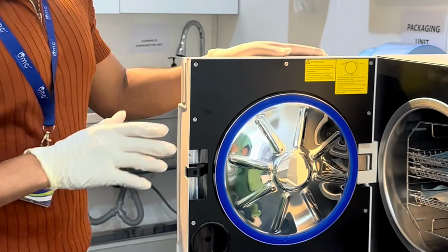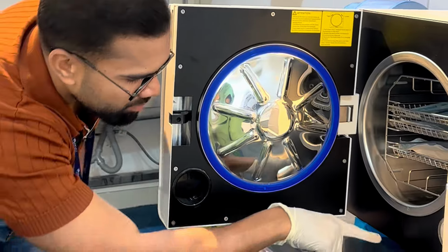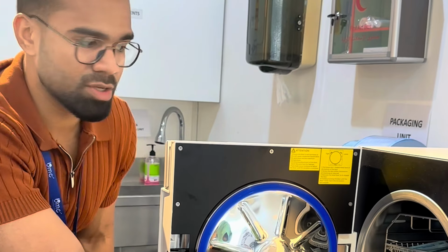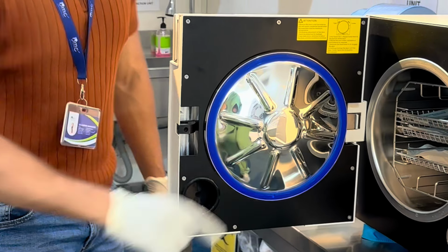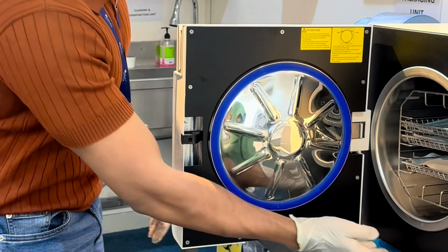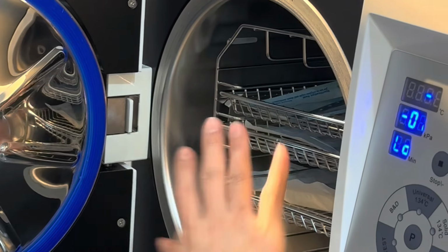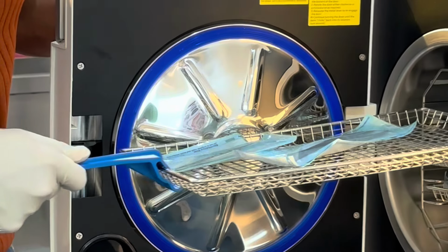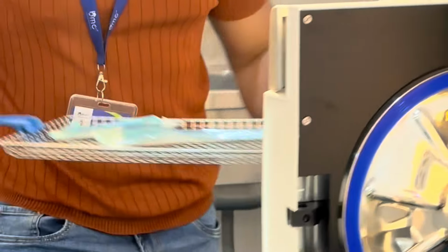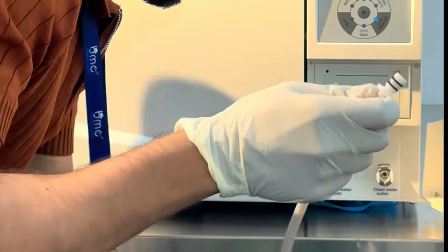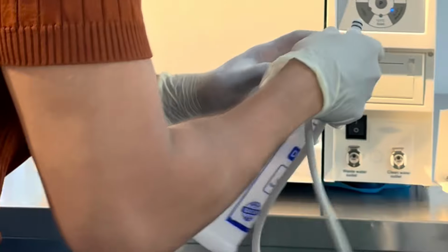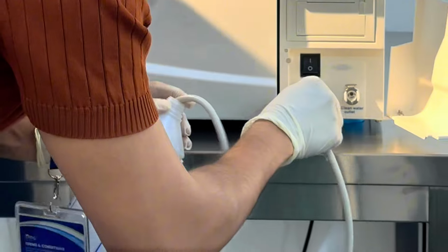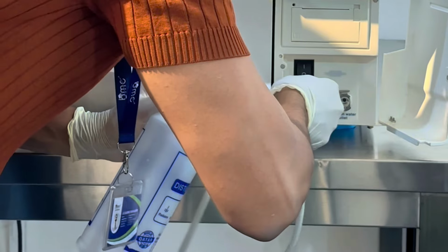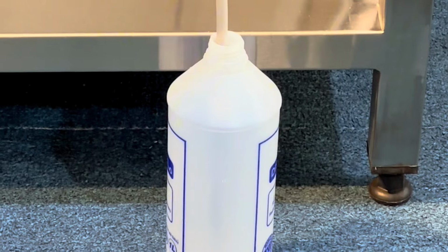After the process is finished, do not open immediately. Allow the chamber to cool for approximately 3 minutes before opening the door, as it will be extremely hot. Handle all instruments with caution, using proper tools to avoid burns or contamination. After unloading, remove them very carefully. Remove any remaining wastewater from the system, following the correct procedure, and clean the chamber if required. When removing the wastewater, always don fresh PPE to maintain strict hygiene.